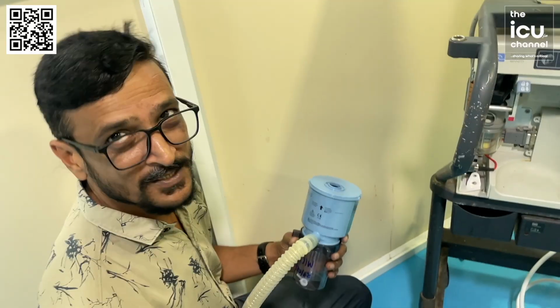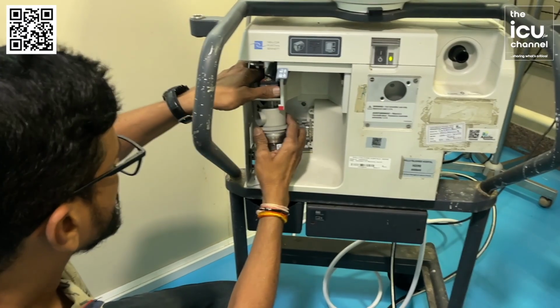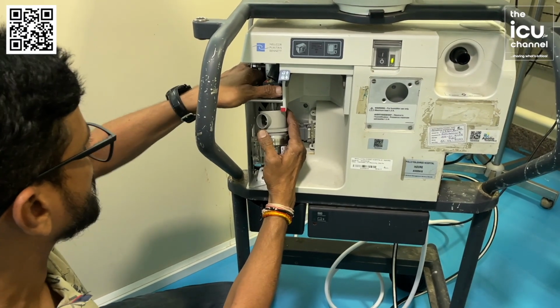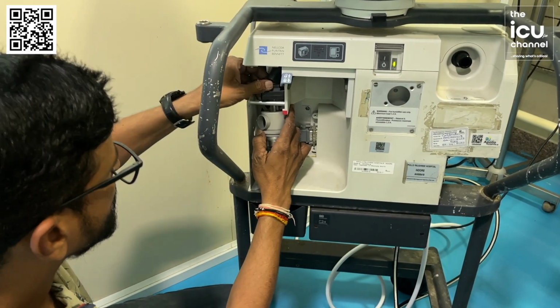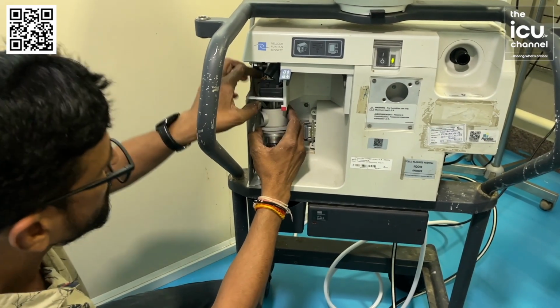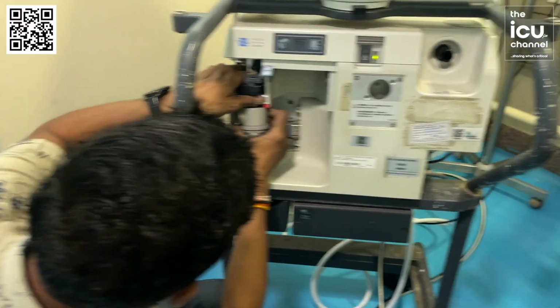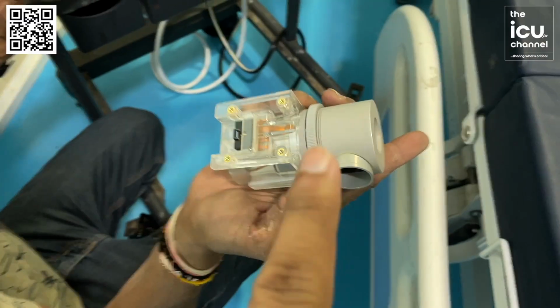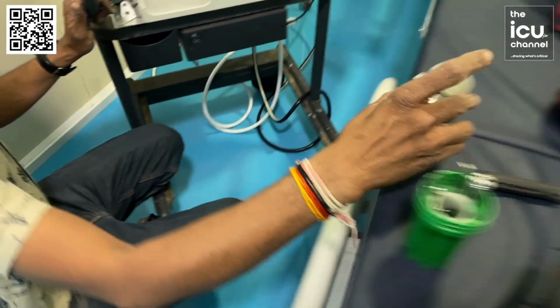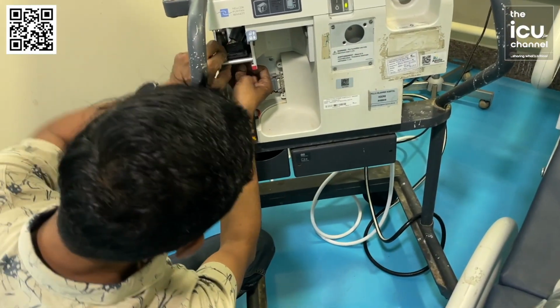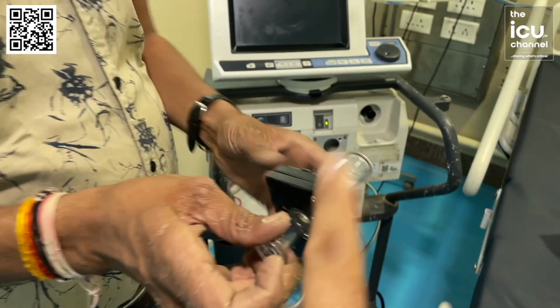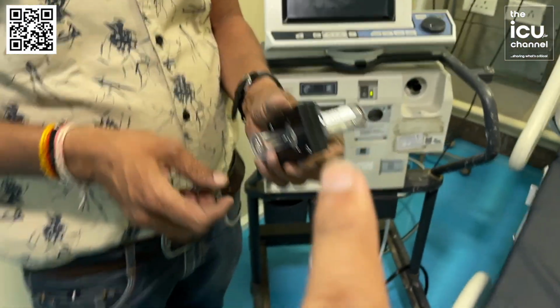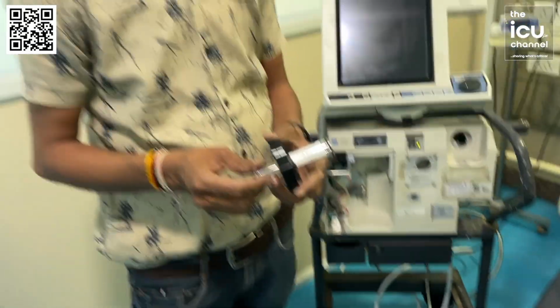It is 1%, 2%. So this valve detects the leak. If it is in the expected amount, it will not give an alarm. But if it is beyond that, there is a leak in the circuit, it will tell us. Okay. And the thing which is coming out is the expiratory flow sensor. It senses how much tidal volume is getting returned from the ventilator patients.